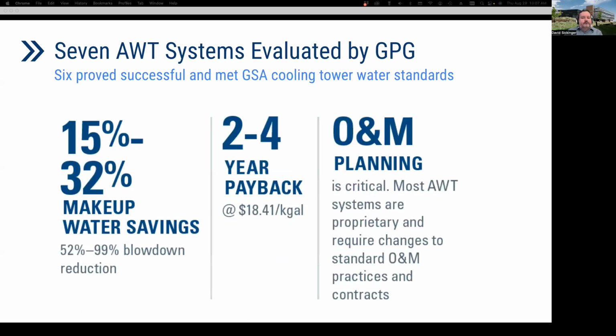Next slide, please. So 7 AWT systems were evaluated by GPG. 6 of these technologies proved successful and met the GSA cooling tower water standards, with makeup water savings ranging from 15 to 32%, resulting in paybacks in the 2 to 4 year time span when applying the GSA average water rate of $18.41 per 1,000 gallons at these testbed sites. These AWT systems aren't necessarily, though, set and forget systems, so operation and maintenance, O&M, planning is critical. Since most are proprietary, changes are required to O&M practices and contracts.